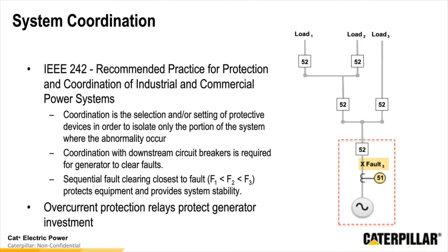And finally, we have the overcurrent protection device. The overcurrent protection device, as we're showing here, is a 51. That's the AC time overcurrent. What we're looking at here is the ability to identify a fault that has now occurred potentially inside the generator or inside that generator set circuit breaker. So we can now send a signal to the generator to turn it off and to stop producing current. And so now we can protect, again, our generator asset. This also works if for some reason one of those breakers that we talked about in the system failed to open. We would still have that 51 device as a secondary level of protection that's protecting our asset overall.